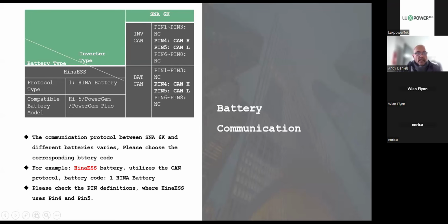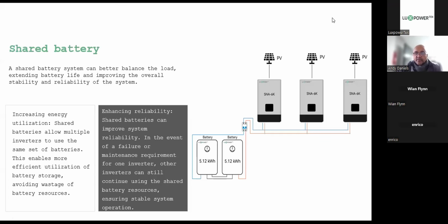Okay, right, shared batteries. Many of you have got experience with this. So the shared battery we use when we typically have more than one inverter. So it's either 2 or 3 in either a single phase or a 3-phase configuration. And it doesn't really matter if you've got one machine on one phase and 3 on another, you know, like unbalanced, we can do that. But we always recommend that you share the battery. And here you will share the battery through a common bus bar.